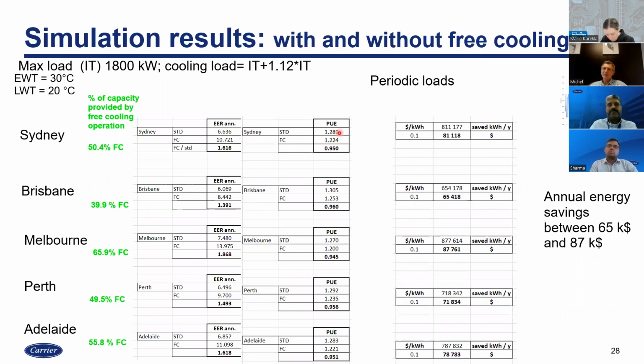Without free cooling, my annual efficiency will be 6.63 and PUE 1.29 with my assumptions. Now if I'm adding hydronic coils, there's additional pressure drop, so I'm penalizing my operation in mechanical mode. But what I gain in free cooling is more than what I'm losing in mechanical mode. So you see here the numbers: 10.72 EER, 1.22 PUE, and this is just taking the unit, connecting water - it's done. So this is what I'm saying: you don't need adiabatic cooling, you don't need bypasses on the water side. It's a package chiller with water in, water out. Everything is inside, and this is the level of improvement you may have.